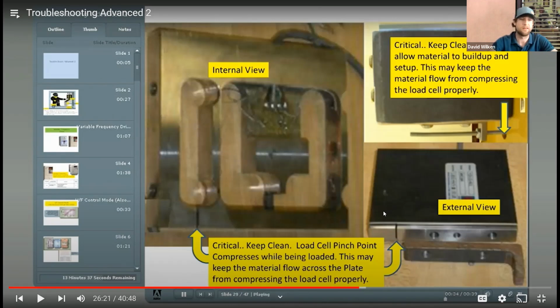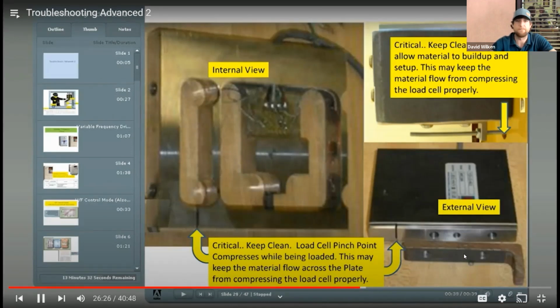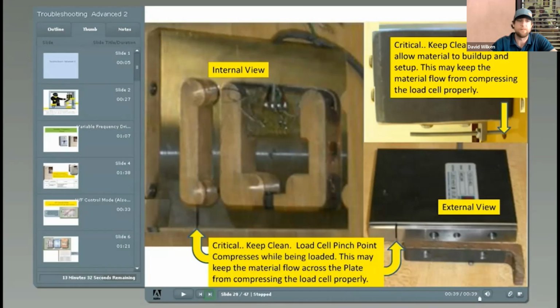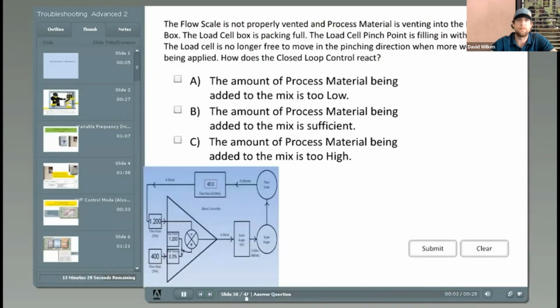Lost Nathan again. The applied load to the load cell can be significantly more than the electrical output signal is indicating. The flow scale is not properly vented, and processed material is venting into the load cell box. The load cell box is packing full. The load cell pinch point is filling in with material. The load cell is no longer free to move in the pinching direction when more weight is being applied.